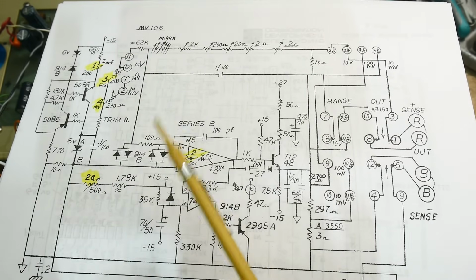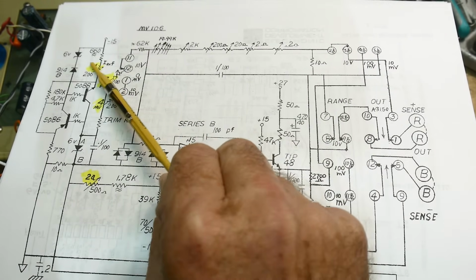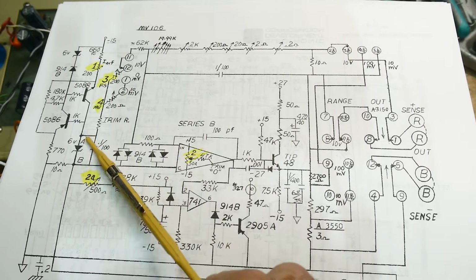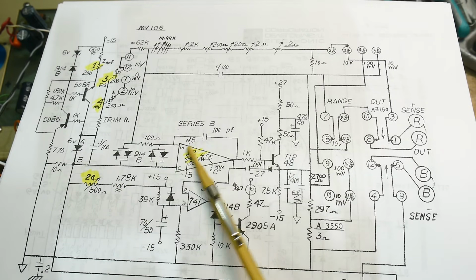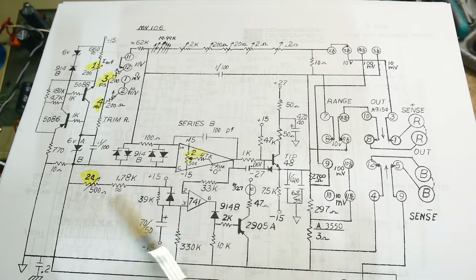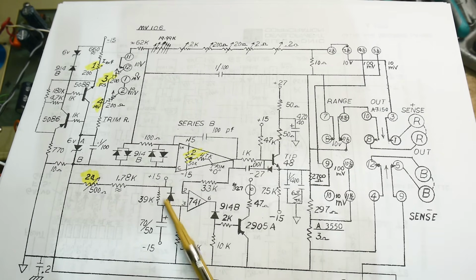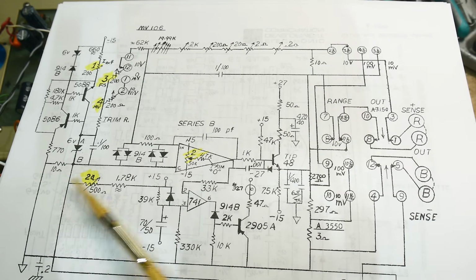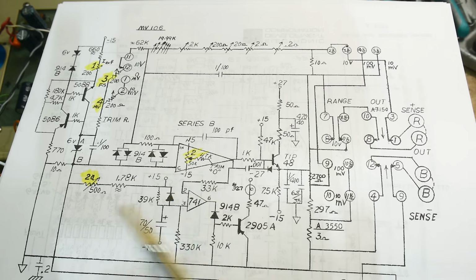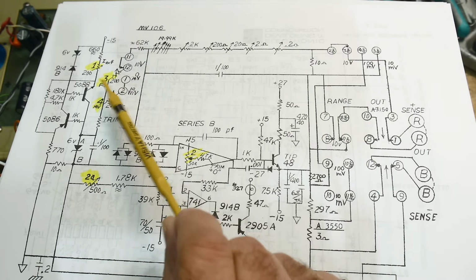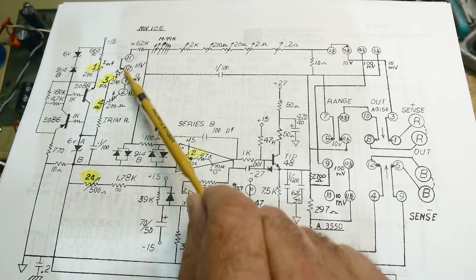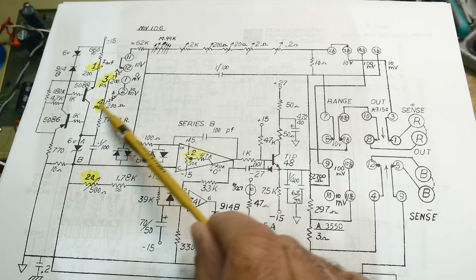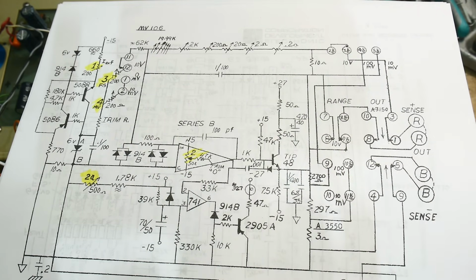So here are the magic things that you tweak. Number 1 sets that reference voltage. 2 is the offset voltage for the op amp here. 2A is the offset voltage for the ground sense line. Make sure that's not introducing any errors. 3 sets the 10 volt range, and 4 sets the 100 millivolt range. And that's all there is to it.